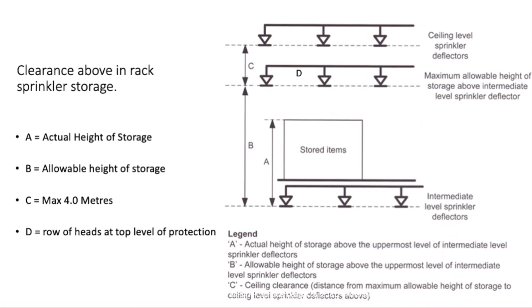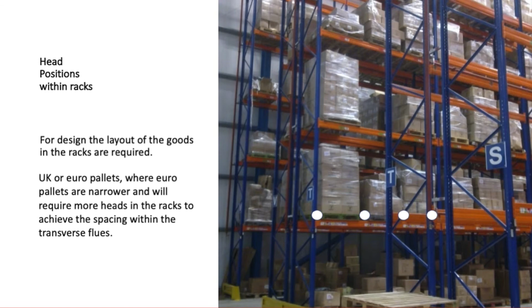So again, head positions in racks. So you can see here what we'll have. You can either have pallets in the UK or Euro pallets. The Euro pallets are slimmer, which means you can fit more pallets inside a bay. Now, typical UK pallets will fit 3 pallets in a bay. So when you've got that situation, the white dots here will show you roughly where the sprinkler heads will be. And that will be dependent on the risk of the goods. It might be at every level, or it might be at every other level. It'll certainly be all the way down the racks in every single transverse flue. So you can get quite a lot of heads in racks. Euro pallets, you would have 5 heads. So if you think about it, 4 heads for UK pallets, 5 heads for Euro pallets. Okay, so it's in every transverse flue. So the management of the storage is vastly important on this.